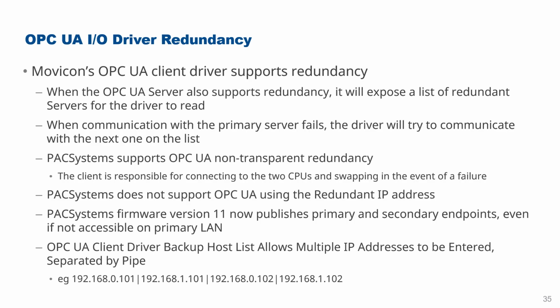So make sure you're using the latest firmware, and you'd also need to look at using the latest version of Movicon, because we have enhanced the OPC-UA capability with successive versions. So 4.4 does update the OPC-UA stack. And also the latest PAC Systems firmware gives you better OPC-UA performance, as well as properly publishing all of the endpoints.